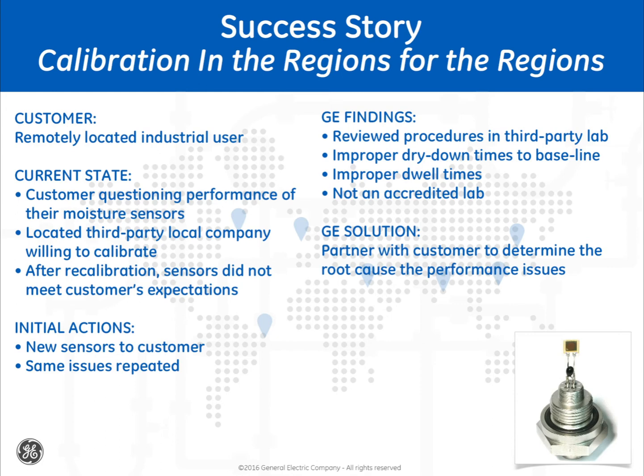The question of the role of the third-party calibration facility was an obstacle in getting to the root cause of the issue. Since the customer had success with our sensors in the past, we sent them new sensors, and the cycle of doubt repeated itself. After months of frustration, a deep dive determined that the calibration procedures the local lab was using did not allow for a proper dry down to baseline, nor for proper dwell times to the different moisture levels, nor were they able to produce any traceability of their calibrations to accredited standards.